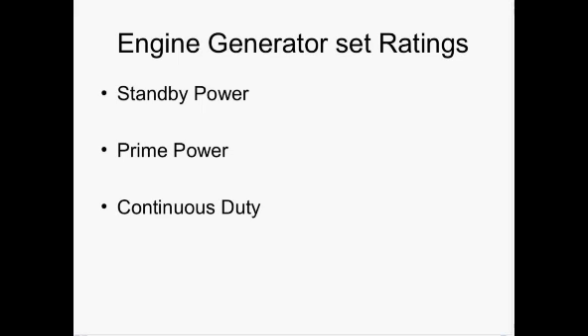A generator set used for backup emergency power must be rated for prime power if it's used for a utility power curtailment program. A continuous duty rated generator set is suitable for running 24 hours, 7 days a week, and is shut down only for maintenance. These generator sets are used in applications where no utility power is available, or where the generator set is expected to base load on the utility grid to add power to the grid over long periods of time. Offshore drilling rigs for oil and gas, mining applications, remote resorts, or a cabin are some examples.